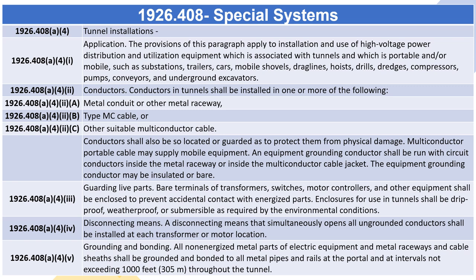1926.408(A)(4)(iii) — Guarding Live Parts. Bare terminals of transformers, switches, motor controllers, and other equipment shall be enclosed to prevent accidental contact with energized parts. Enclosures for use in tunnels shall be drip-proof, weatherproof, or submersible as required by the environmental conditions.